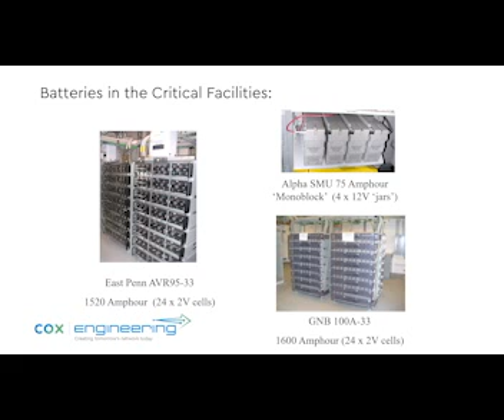Here's some examples of valve regulated lead acid batteries. On the left and on the bottom, you see large 1600 amp hour stacks - 2000 amp hour stacks are available these days. Each of those 2000 amp hour stacks will power probably about 500 amps of load for about 3 hours, let's say. And the smaller monoblock batteries in the upper right, you'll see those in outside plant, maybe business services cabinets, customer premise sites where you have DC plants and need battery backup there. A lot of us used to use the 8-hour backup at customer prems and cabinets from the telecom world.